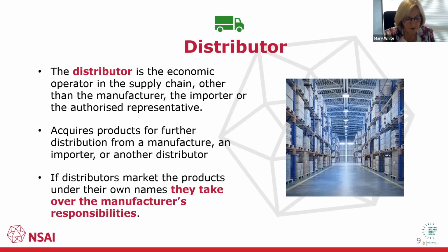If a distributor markets products under their own name, they take over the manufacturer's responsibilities. In this case, they must have sufficient information on the design and production of the product because they will be assuming the legal responsibility when affixing the CE marking and drawing up the declaration of conformity.